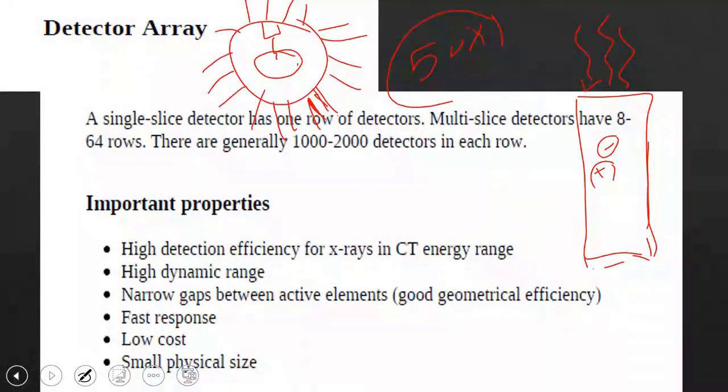Is everything okay? Consider that not all tubes will be perpendicular to the X-ray beam. The transmitted X-ray beam might come at a certain angle, while the detector itself, whether a gas-filled detector or a xenon detector, won't align with the direction of the X-ray beam. This reduces the geometric efficiency of the gas-filled detector, so they decided to replace it with solid state detectors.